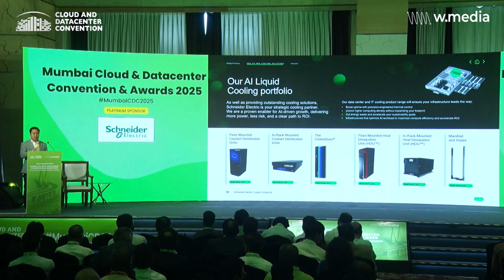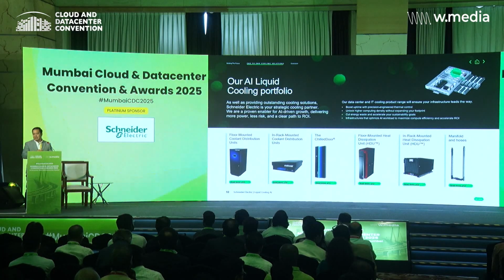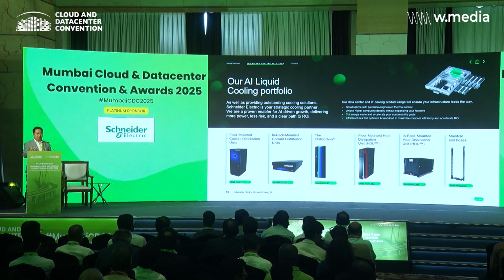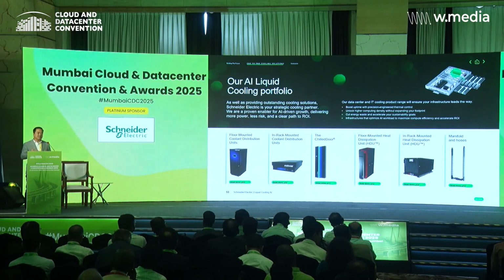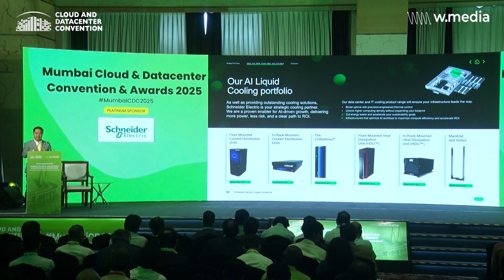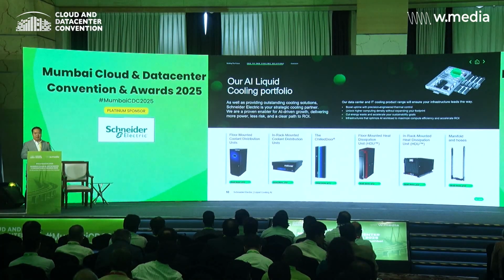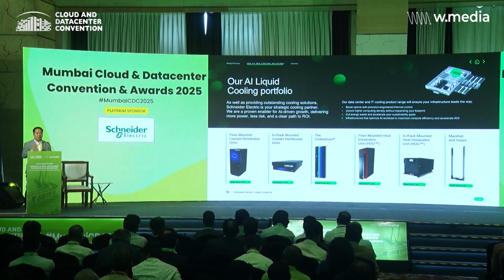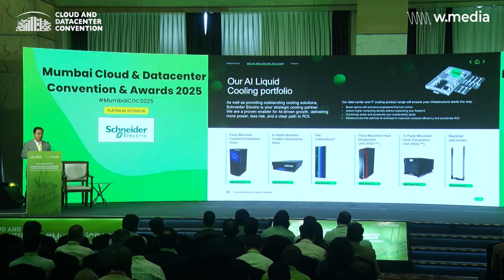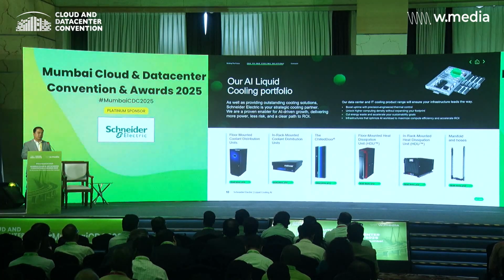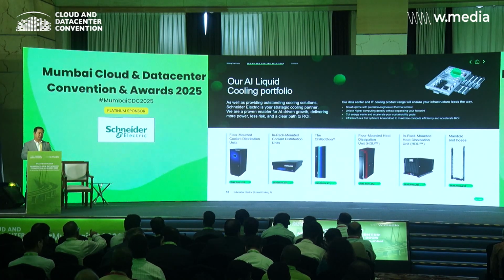Also, chilled doors, up to 77 kW per rack. They're able to cool 100% air-cooled H100s, but beyond that, these units can also cool 40-50 kW per rack, which is ideal when coupled with high-density servers today. At 130 kW, adding a rear door, you're guaranteed to have the air side and liquid cooling all managed by the same loop and the same vendor, ensuring correct interfacing.